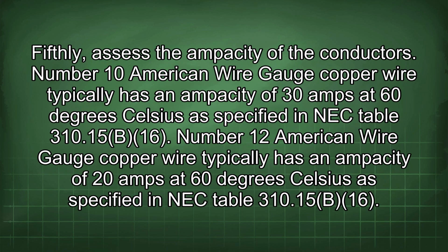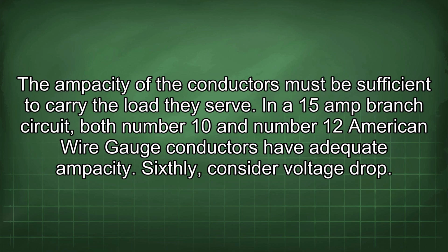Fifthly, assess the ampacity of the conductors. Number 10 American wire gauge copper wire typically has an ampacity of 30 amps at 60 degrees Celsius as specified in NEC Table 310.15(B)(16). Number 12 American wire gauge copper wire typically has an ampacity of 20 amps at 60 degrees Celsius as specified in NEC Table 310.15(B)(16). The ampacity of the conductors must be sufficient to carry the load they serve. In a 15-amp branch circuit, both number 10 and number 12 American wire gauge conductors have adequate ampacity.